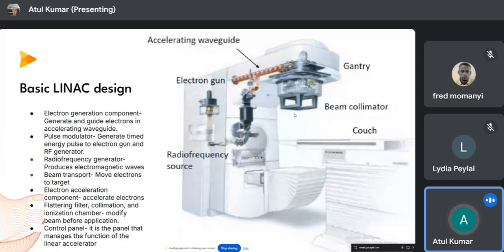After the beam passes through the body, we have a detector here. This is called EPID, or electronic portal imaging device, which can detect how much X-ray is coming through, and it is used for several other purposes. So this is the basic design of a LINAC. In some LINACs, you also have arms around, like the two arms I showed in the previous image, a KV generator and a KV detector, used for proper localization of the patient. That is an addition to the LINAC.